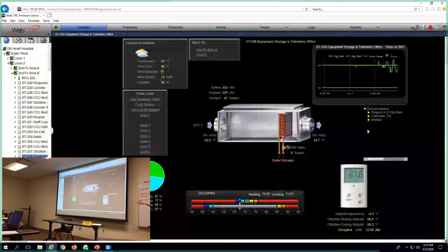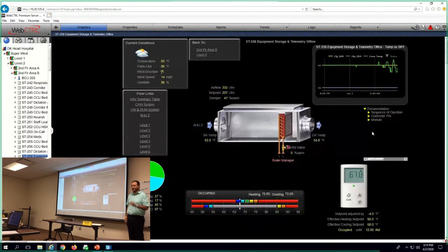Once TME gets all the as-builts done for the mechanical system, we could put that as-built drawing on the floor plan, where you could click on it and go see it. At least it would get you in the ballpark of where that VAV is, where you start popping your head in looking. And it has the CFM numbers on the mechanical drawings, if we get the ductwork drawings. And the mechanical drawings with the ductwork and everything are really full. There's a lot going on in those drawings.